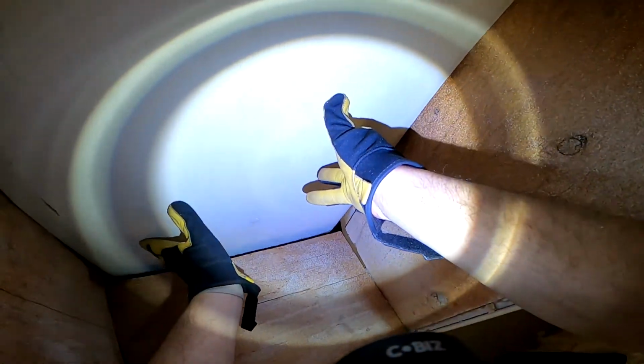So let's get to the attic. It is evenly insulated. It's just under insulated. There's roughly 6 inches of loose fill fiberglass, which equates to an R value of about 16. And in our region of Maryland, we want to be R49. So I want you to take note of those two triangular insulated areas back there, the ones with the yellow insulation, and those are your skylights.